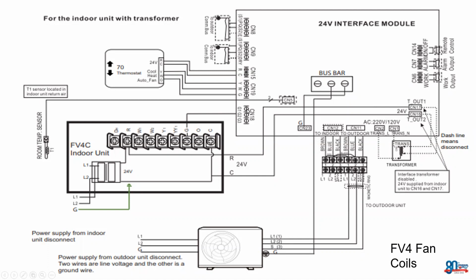Okay, now finally, we need to focus on what's going to run our fan. We want to look over to CN18 here, which has G1, G2, and G3 terminals. These are individual outputs for our fan speed. Now with the FV4, we only need to focus on one of them. So we don't want to wire G1, G2, and G3 all back to the G terminal at the FV4 printed circuit board because we'll cause a direct short, and of course nothing's going to work.